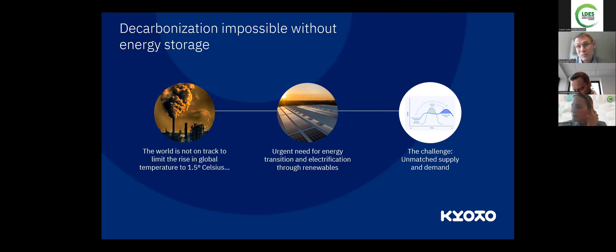You need a thermal battery if you want to produce heat. So basically what we have developed is a flexible energy storage system that is able to deliver heat on demand. It can discharge in the form of steam. It can also potentially discharge in hot air or liquid if that is needed. We generate the heat while the energy is cheap, and then we can dispatch it whenever the customer needs it.